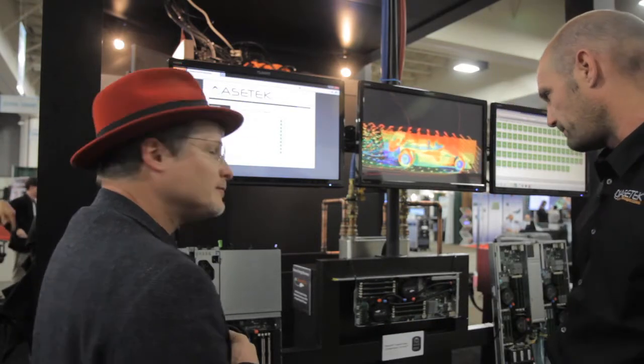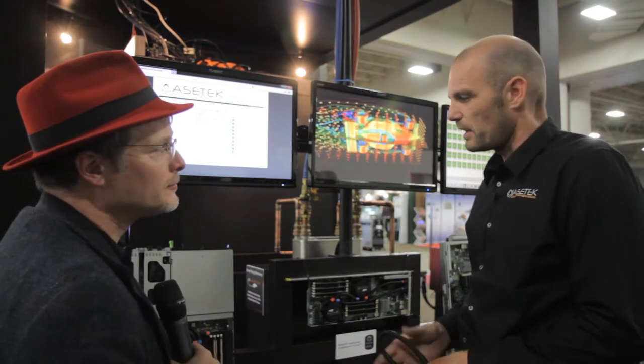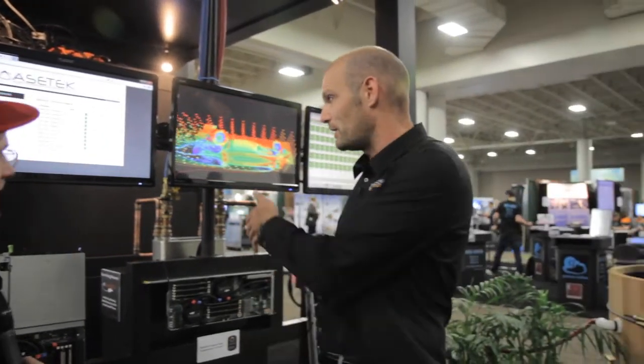Something we haven't talked about is the actual energy savings on your power bill. What we also have here is essentially a small power plant, since there's so much waste heat from these servers you can recapture it, for example for building heating. Over here we have a hot tub heated by these servers, currently around 110 degrees. So not only do you save money on cooling, you can reuse the heat and save money that way. So you could heat your building with the waste heat removed from the computers. Exactly.